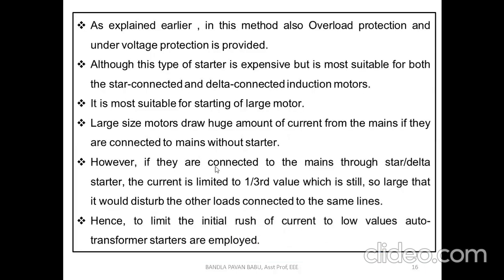Next, however, if they are connected to the mains through a star or delta starter, the current is limited to 1/3 value, which is still so large that it would disturb the other loads connected to the same line. The problem is that with high rating machines, any variation in the line, whether 1/3 or 1/5 times, is going to disturb the other loads connected in parallel. In the previous session I also said that if all the machines are connected to the transmission lines, any variation in one machine will obviously disturb the other machines and cause variations in the line. Hence, to limit the initial rush of current to low values, auto transformer starters are employed.